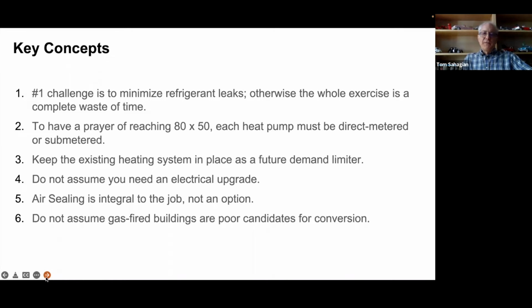Another issue a lot of folks are concerned about is that they're going to have to spend big money to upgrade the electrical system in the building. In this project, we did not have to do that. The service to each apartment was actually quite low, only 40 amps times 2, which is roughly the lowest I've seen in most apartments in New York. So if your building has more than that, you almost certainly will not have to do an electrical upgrade, which is a huge money saver.